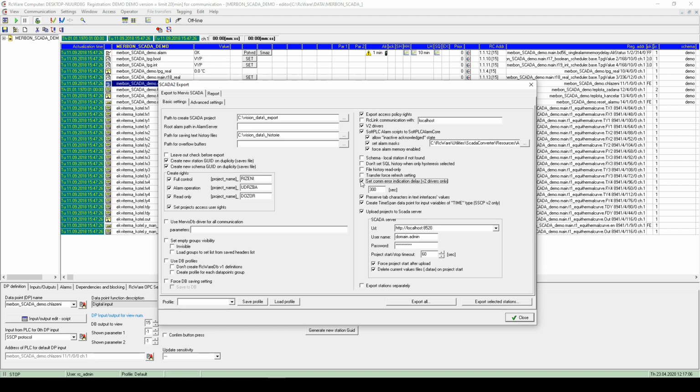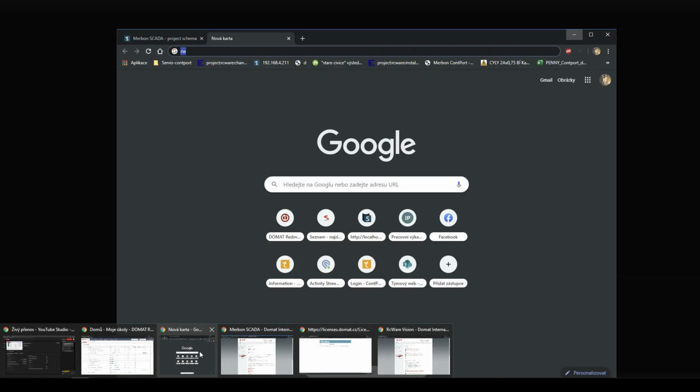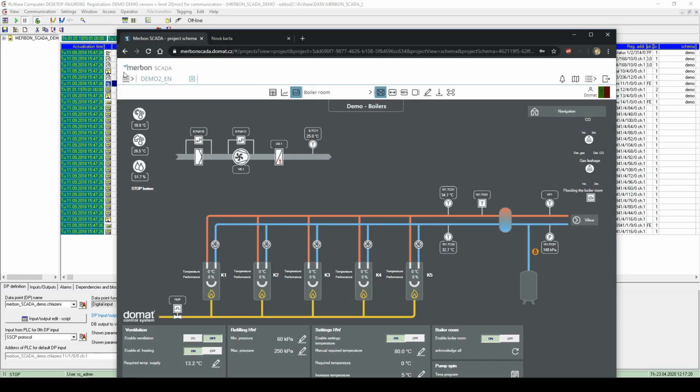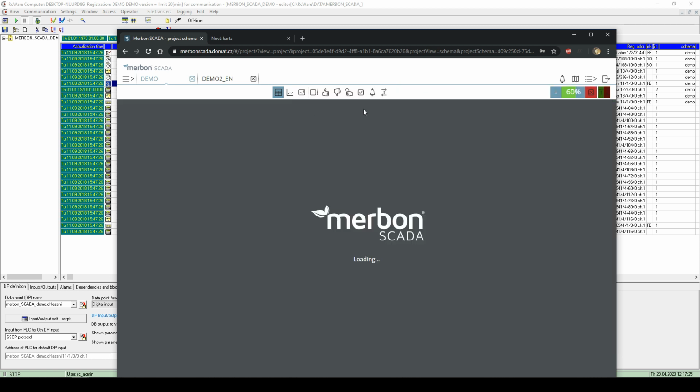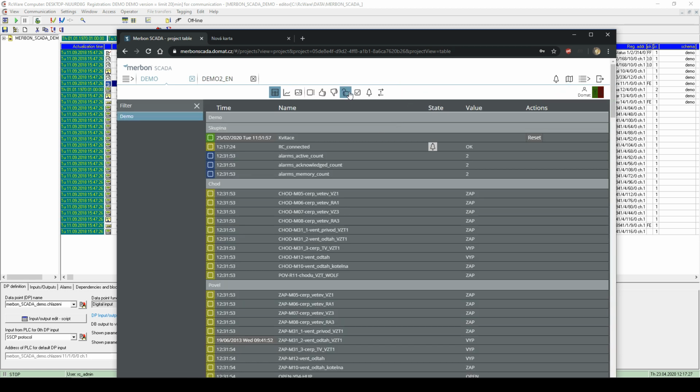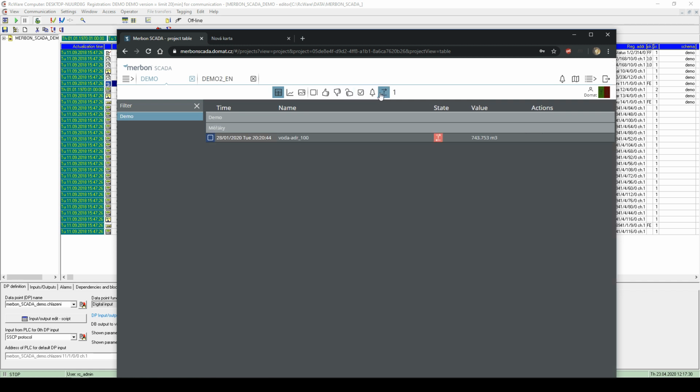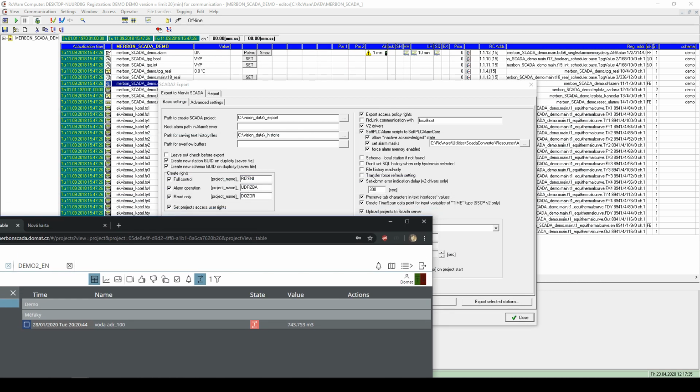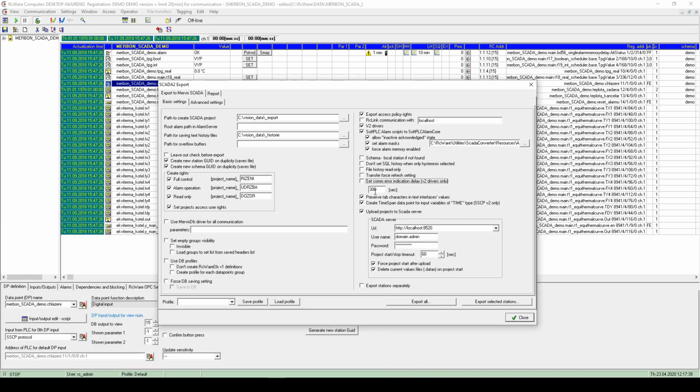Then you can check this option, and then you can add the delay for your communication alarm. You see, it was what I showed you here. In the first one there was some communication error. So this will show only after the delay, in case you check it. In case you don't, it will show immediately.